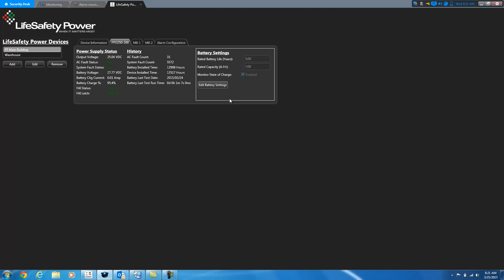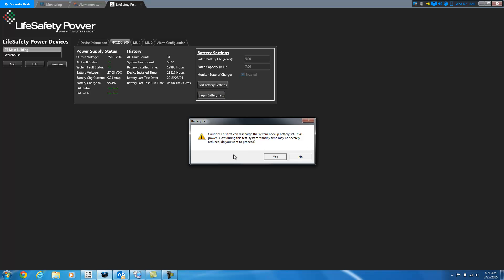So once I've turned it back on, this will refresh in just a second, and the begin battery test becomes available. When I click begin battery test, you get a warning that says that basically we're telling the board to run on battery power. So if the battery is not fully charged when you do this and you start the test and you have an AC failure that goes for an extended period of time, because the battery is always discharging, if it completely discharges and tries to switch back over to normal AC power and there's no power there, your board's going to power down. So this is just a warning making sure to let you know that you want to do this test when you have solid AC power and there's not going to be any kind of power outages.